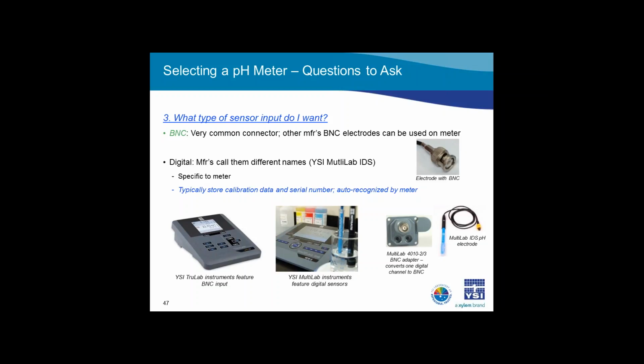Another common type is the digital connector. These are specific to each manufacturer, so they don't have the same flexibility as BNC pH electrodes. However, there are major advantages to a digital connection, as these sensors store their calibration data and their serial number. They are also auto-recognized when connected to the meter, so there is no need to tell the instrument what is connected. Our Multilab 2 and 3 channel instruments are digital, but they also allow the connection of a BNC electrode if a BNC adapter is installed. This allows the user to connect both digital and BNC pH sensors.